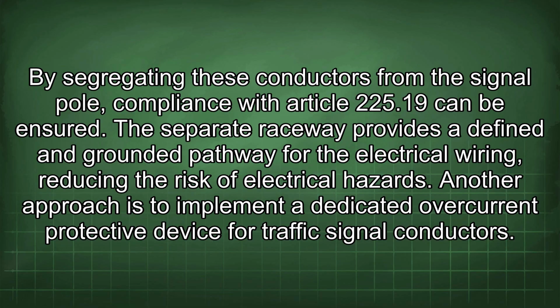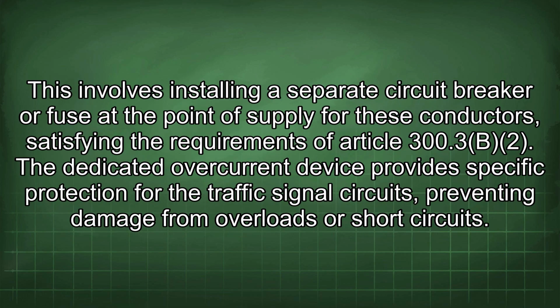Another approach is to implement a dedicated overcurrent protective device for traffic signal conductors. This involves installing a separate circuit breaker or fuse at the point of supply for these conductors, satisfying the requirements of Article 300.3(B)(2). The dedicated overcurrent device provides specific protection for the traffic signal circuits, preventing damage from overloads or short circuits.